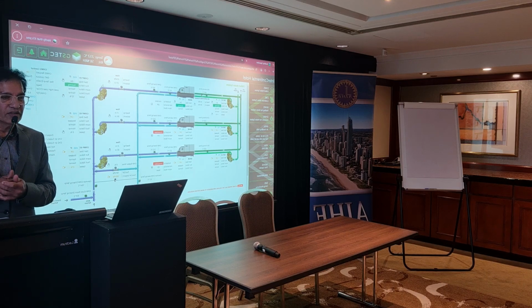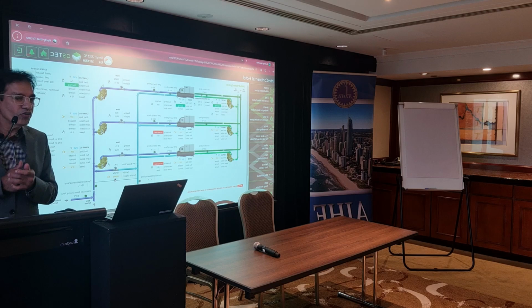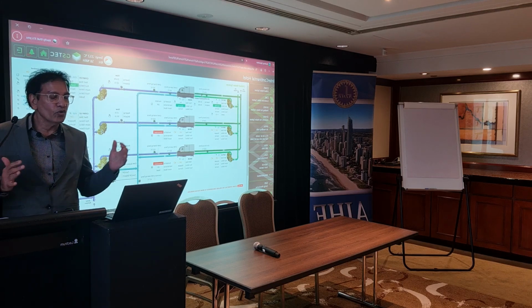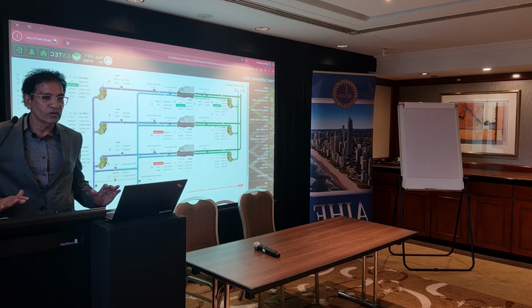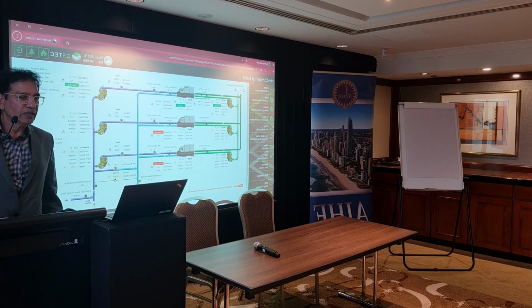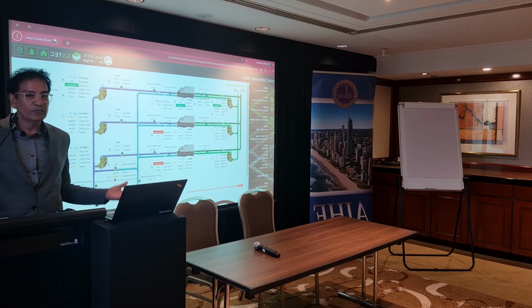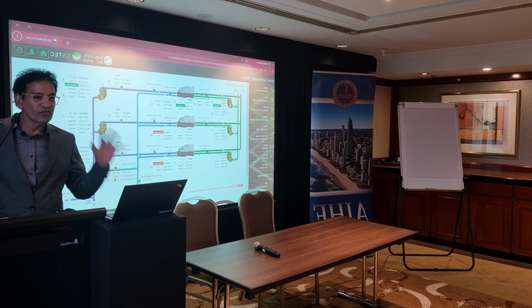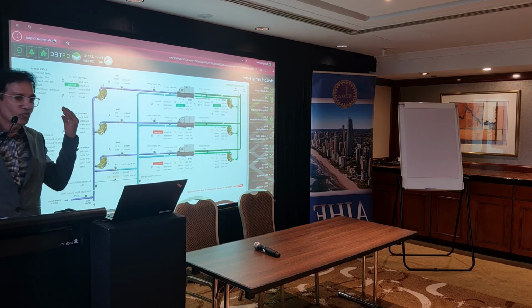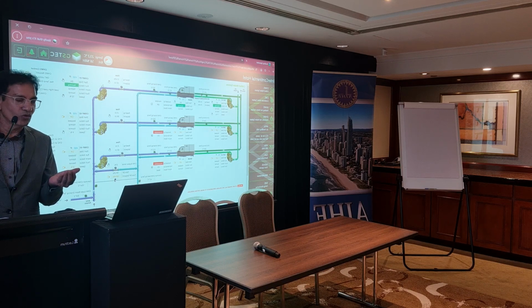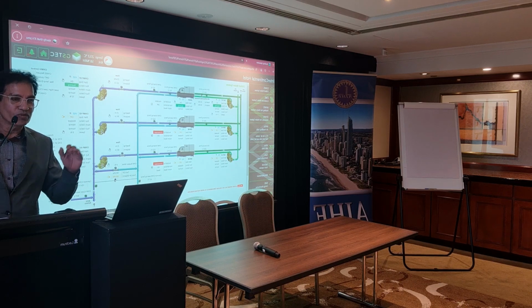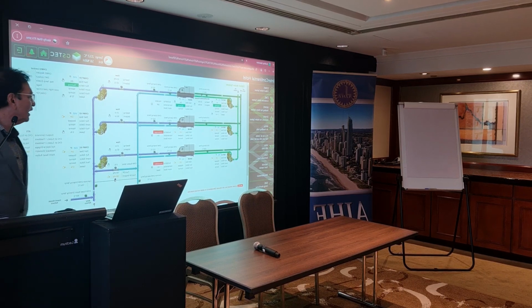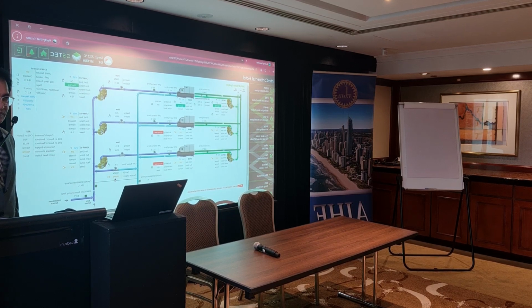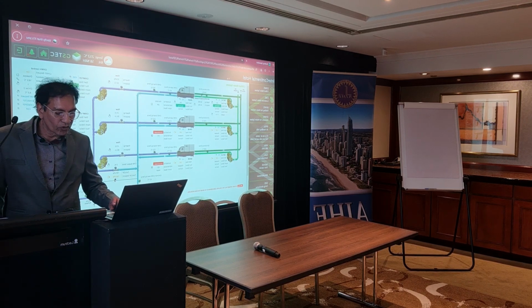All we need is alarms and alerts, that's all, on a dashboard. Their original strategy was that they could cycle the chiller off or down based on guest room demand. I said, why? How can you do that? If there are 5 rooms calling for cooling, it's calling for cooling. The chiller will give you whatever set point chilled water it gives you, and it will modulate. So you're not going to shut down the chiller. If there's a demand, you have to supply that demand. So then they agreed and said that they are not going to put that in.